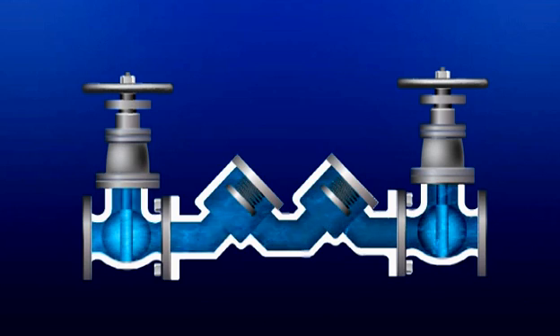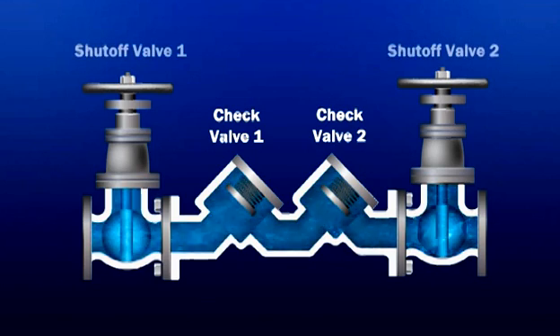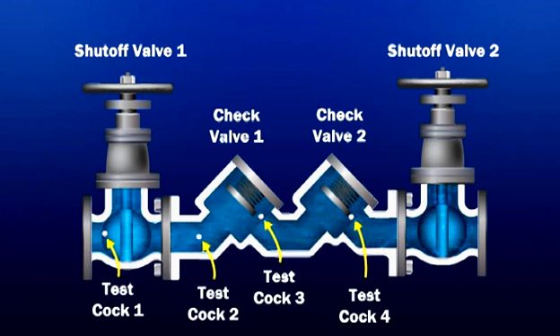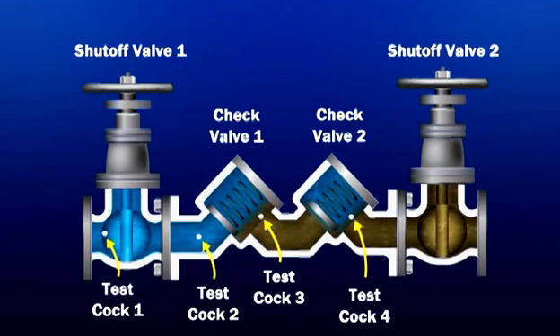The double-check valve assembly consists of two internally loaded independently operating check valves installed as an assembly between two resilient seated shut-off valves and four properly located test cocks. In normal operation, the check valves will open to allow water to pass through. In a back pressure situation, the second check should close. If it doesn't seal properly, the first check will back up the second.